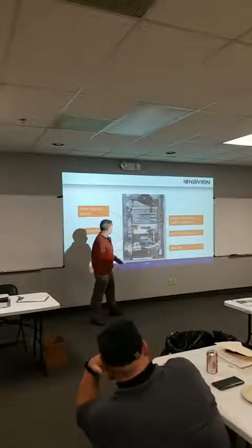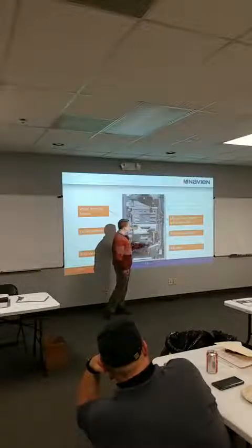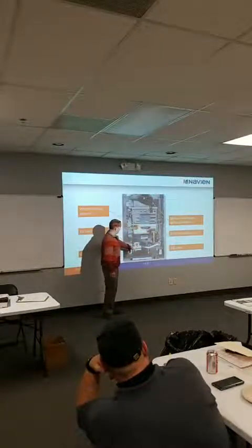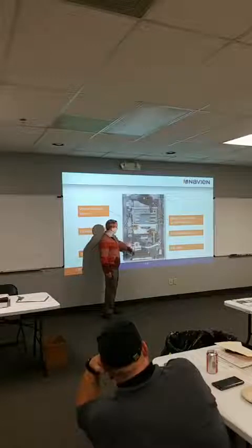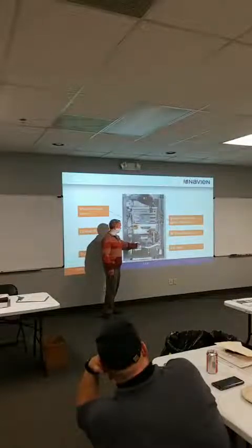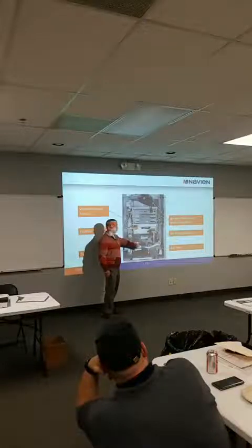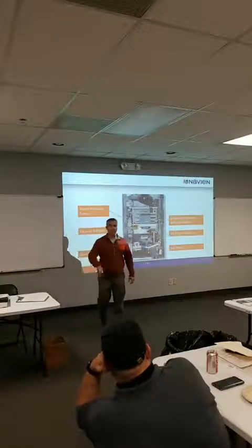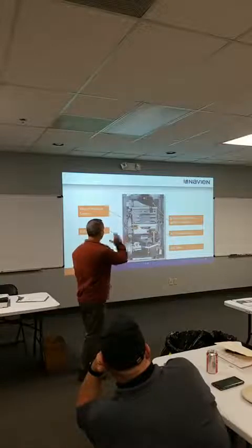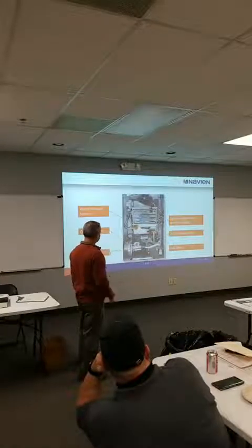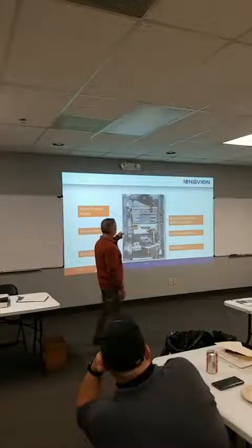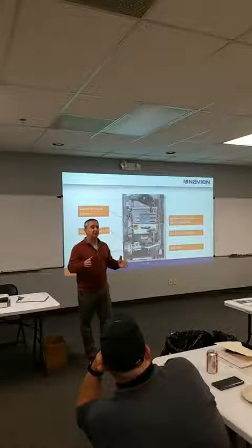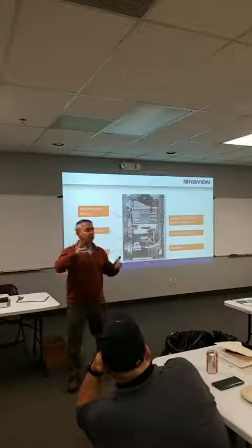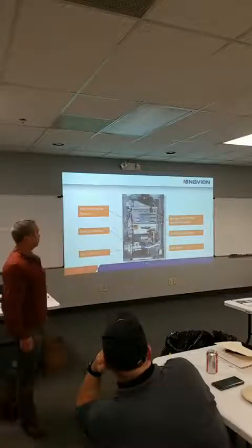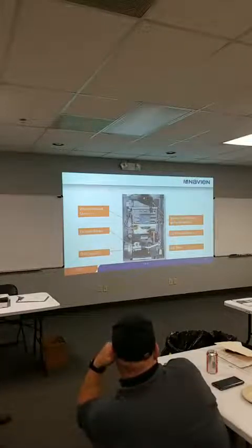So our gas bar is always going between the gas valve and the venturi here. When you ever do an LP conversion, the gas bar has to come off, and your LP conversion orifice is always right there on the dual venturi. And it's just a dip switch setting. So most of the equipment is going to look very similar. When you go from our water tube heat exchanger to our fire tube heat exchanger, the box is going to get bigger, and of course, we're moving some of the internal components around inside the unit.